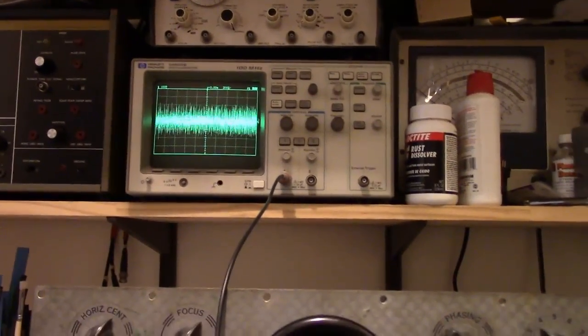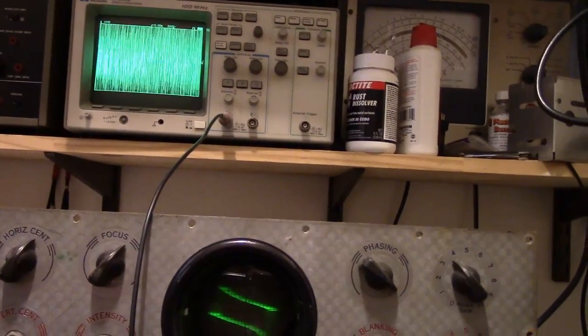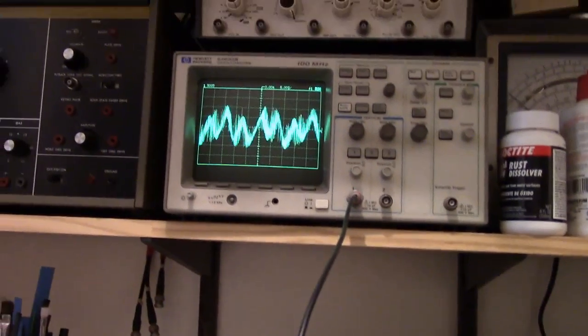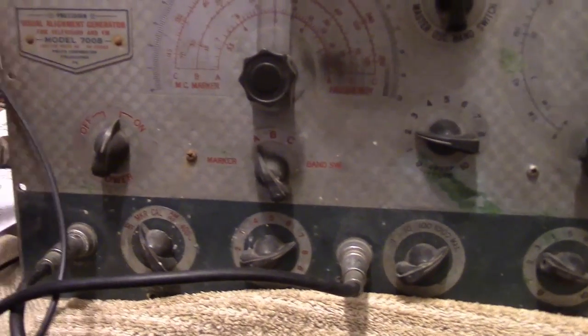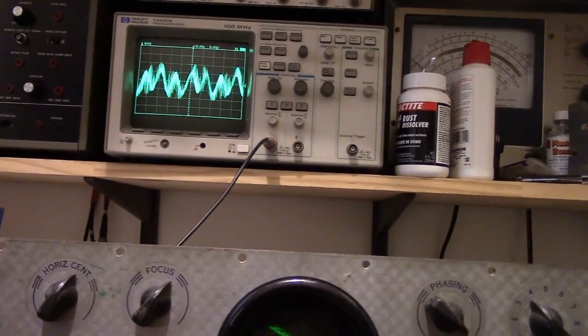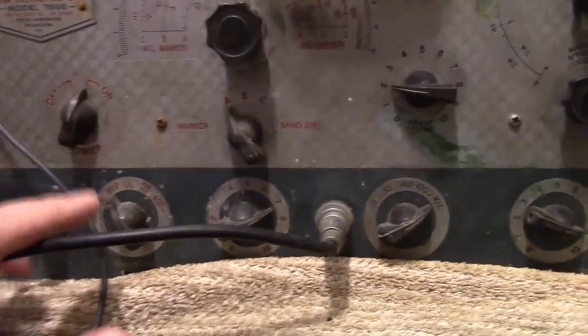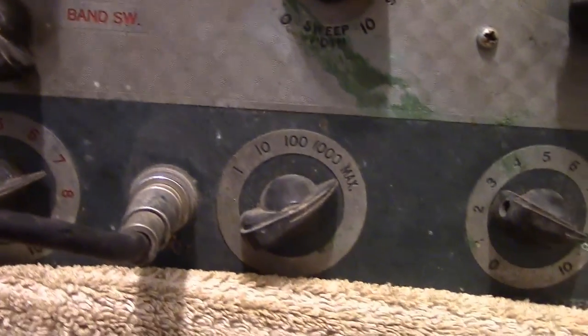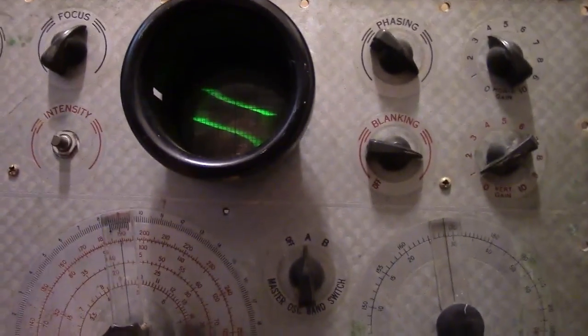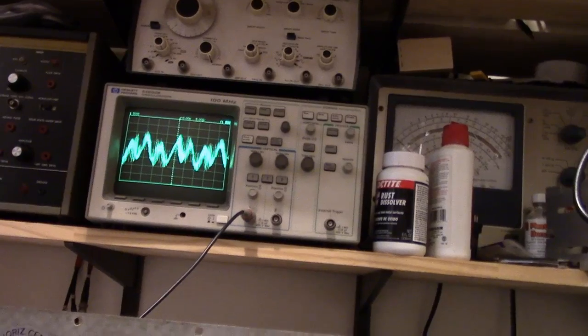Well, checking the step attenuator here. When I got to that, sure looks like we got something. I'm checking the variable level, and it looks kind of messy. Thought it'd be a fairly pure signal, and varying this isn't doing anything. Band switch A should be the lowest frequency band. I would expect it to be varying in frequency. Does that change this? Oh, but this is having an effect. The marker might not do what I think it does, which could also very well be the problem.